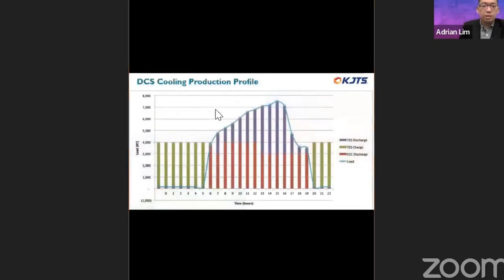With this installation, as shared earlier, we're able to benefit by utilizing a special electricity tariff from the electricity provider. Basically, we run the chillers at night to charge up the tanks, storing cooling energy into those 2 tanks. We save from the lower utility charges imposed during charging, and then discharge the cooling energy during the day when there's demand, supplementing the required cooling load instead of running all the chillers, which would be more costly.